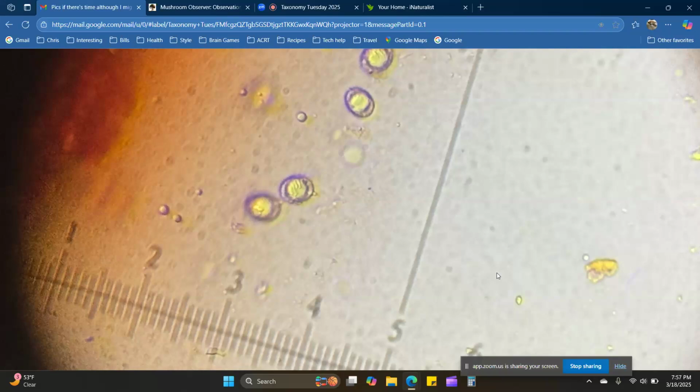And there's another part that's the diaphragm. Is that like the iris that opens and closes? Yes. That's going to change the amount of light coming through the lens. So the condenser, that is. I like to keep the condenser about halfway between my stage and the light source, the illuminator. It's mobile, so you should be able to play with that adjustment.